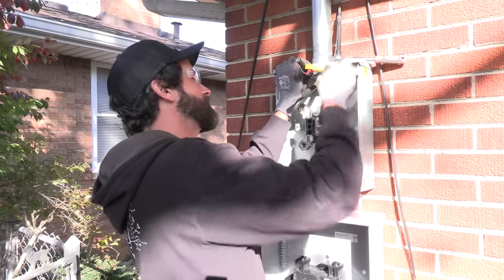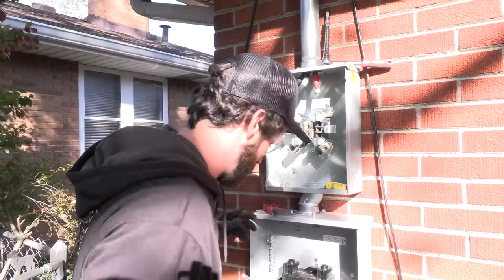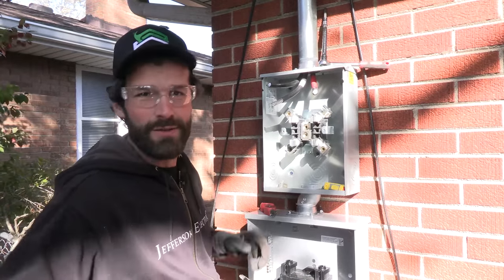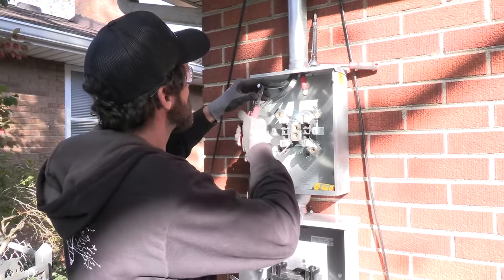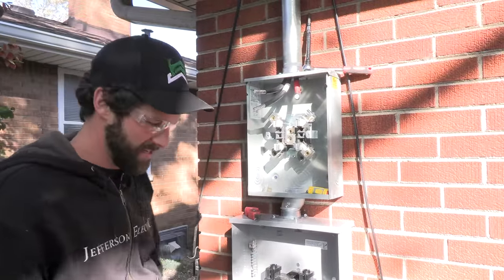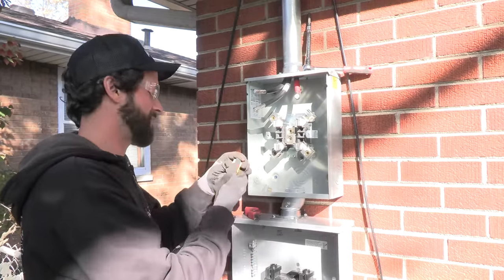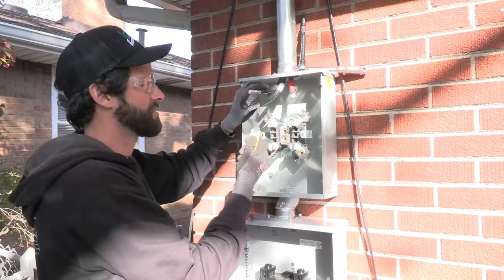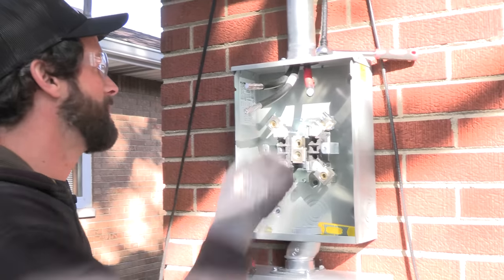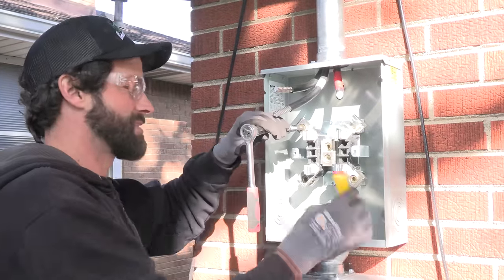Here's my new favorite tool — the Jonard strip tool. The only thing I might be missing is that after using it to score, I need a utility knife blade to get that final piece started. It comes off clean, but I shouldn't have to pull out another tool to finish it. I can't get the insulation off with gloved fingers, so Jonard is about nine out of ten right now — it's just that final step. Maybe I'm missing something, so drop it in the comments.